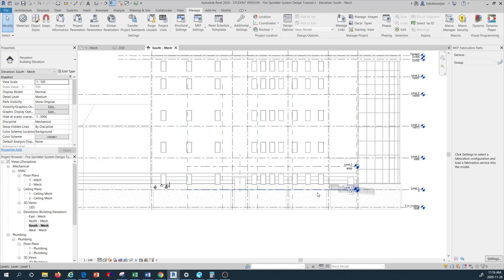On top of alignment, we also want to monitor our model levels in coordination with the architectural levels, because in the architectural world spaces are changing multiple times. Any changes in elevation, ceiling, and those kinds of things impact the way we model the mechanical and sprinkler system. Once any changes happen in the architectural model, we reload the link and get a warning showing that coordination is required, prompting mechanical or sprinkler system designers to modify their design accordingly. This is a very beneficial tool when working collaboratively with other disciplines like architectural.